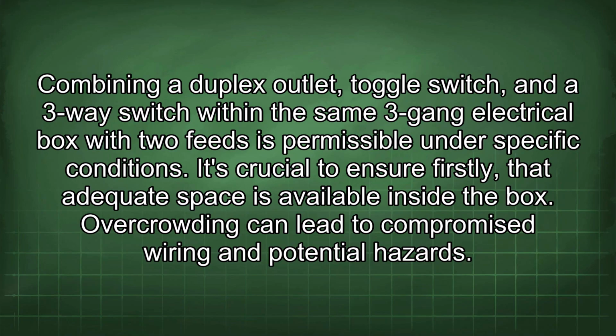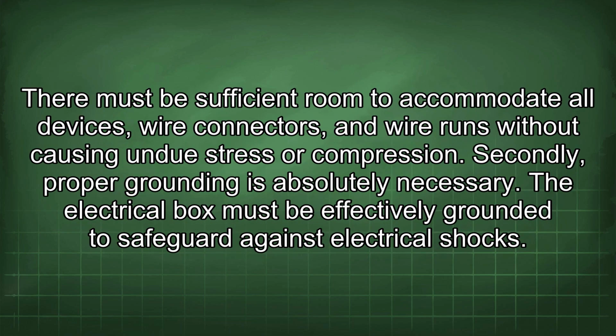Combining a duplex outlet toggle switch and a three-way switch within the same three-gang electrical box with two feeds is permissible under specific conditions. It's crucial to ensure firstly that adequate space is available inside the box. Overcrowding can lead to compromised wiring and potential hazards. There must be sufficient room to accommodate all devices, wire connectors, and wire runs without causing undue stress or compression.